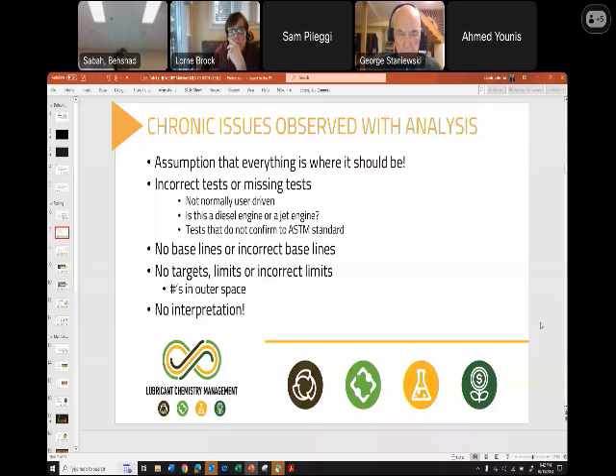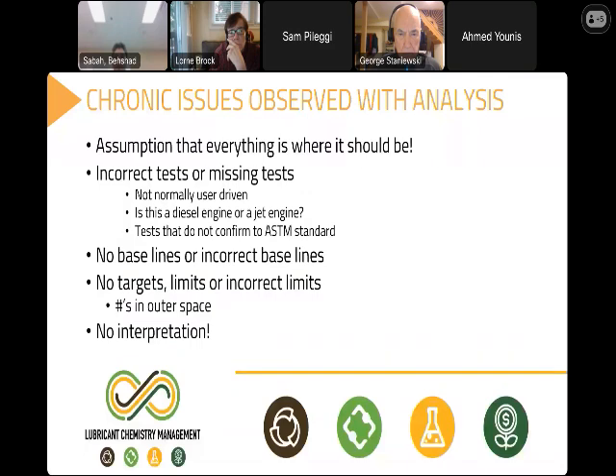So this one plant, I was talking to the plant manager, and I'm looking at these numbers, and I'm quite alarmed. I say, sir, you are 1,000% above condemning limit. He was absolutely shocked. Meanwhile, they're generating 40% of the power in this country at that one facility. So how is this happening? It's like engineers, managers, leaders have literally hundreds, if not hundreds and hundreds of responsibilities. This is one area that can be quickly fixed for not a lot of money, right?